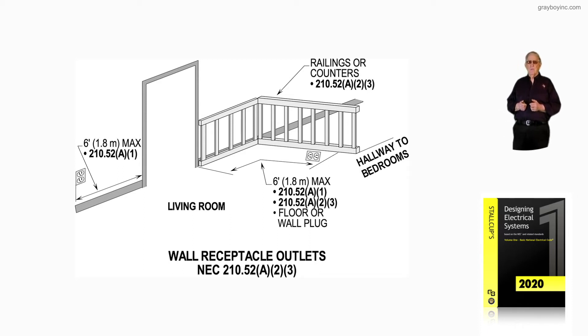Notice to the left of the door, if you're entering in through the door, we have railings. There is a receptacle that's either in the floor within 18 inches, or the railing is built with an area to place your plug. It's placed within six feet, so that's fine.